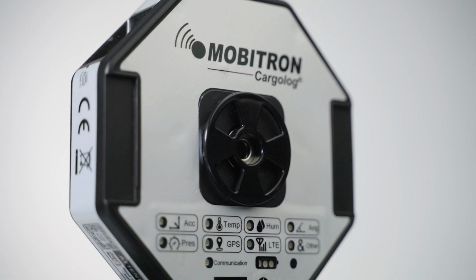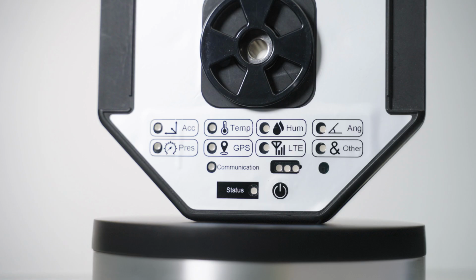When you press the button and the device is not programmed, the status LED will show red. If the LED is yellow, it means the device is programmed, but the measurement hasn't started yet. A blinking yellow LED indicates the device is programmed, but you need to start the measurement manually. To start it manually, you need to hold the button down for 10 to 12 seconds. During this time, the LED will change from blinking yellow to solid green, indicating that the measurement has begun. Now you can release the button.